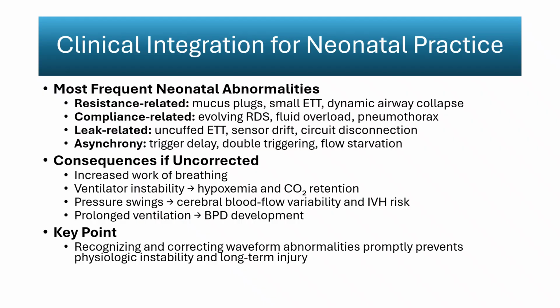In neonatal ventilation, most waveform abnormalities fall into a few recurrent categories. Resistance-related changes are extremely common because neonates have very small endotracheal tubes and highly reactive airways. Mucus plugs, tube narrowing, and dynamic airway collapse all increase resistance and immediately distort both flow and pressure waveforms. Compliance-related changes appear frequently as well, especially in infants with evolving respiratory distress syndrome, fluid overload, or pneumothorax. These conditions stiffen the lung, reducing the volume delivered for a given pressure and altering the shape of the pressure-volume loop. Leak-related issues are another major source of waveform distortion in neonates.